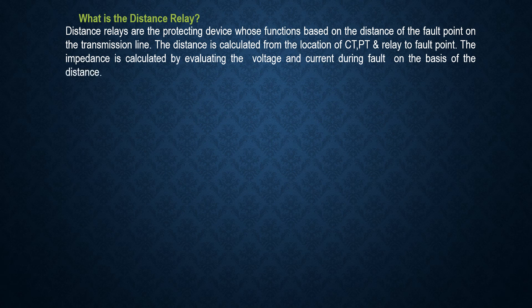What is a distance protection relay? Distance relays are protecting devices whose function is based on the distance of the fault point on the transmission line. The distance is calculated from the location of the relay up to the fault point, and the impedance is calculated by evaluating the voltage and current during the fault.